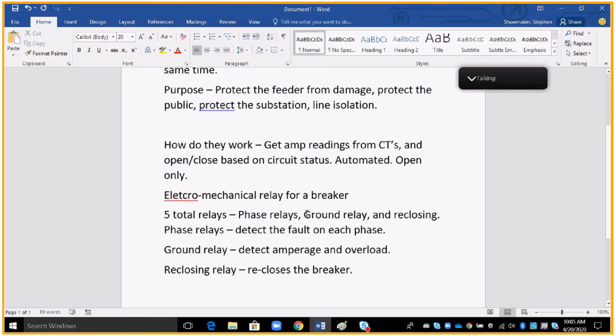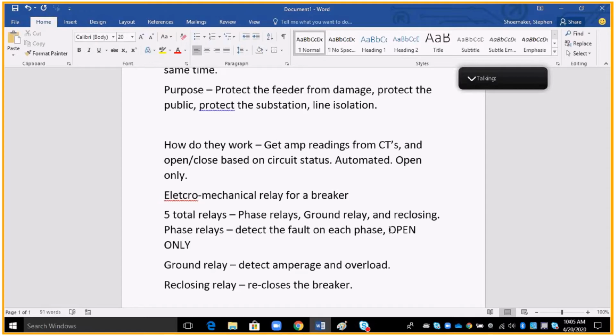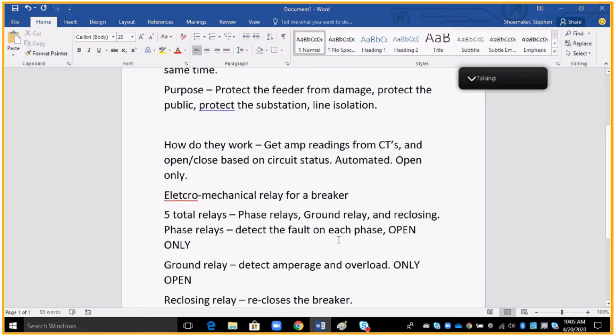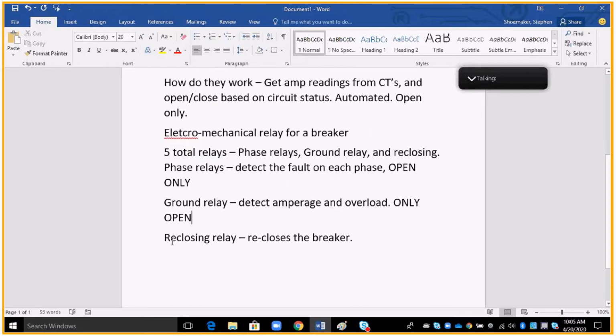All right, so 5 total relays: phase relay, ground relay, and reclosing. Phase relays detect a fault on each phase. Big one: open only. The phase relays only open the breaker. That's all they do. The ground relay is the same. Only open. So it takes another relay to reclose the breaker.